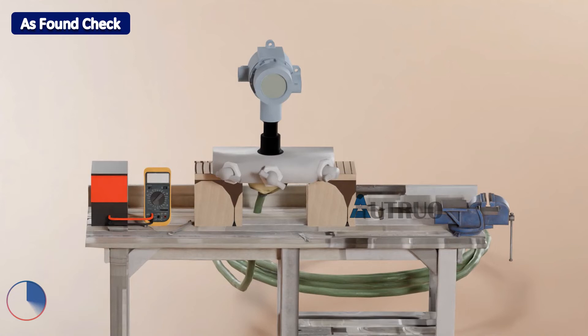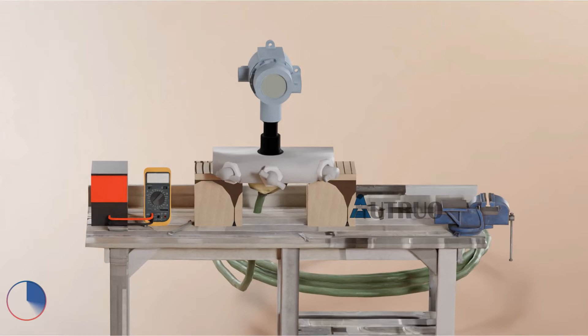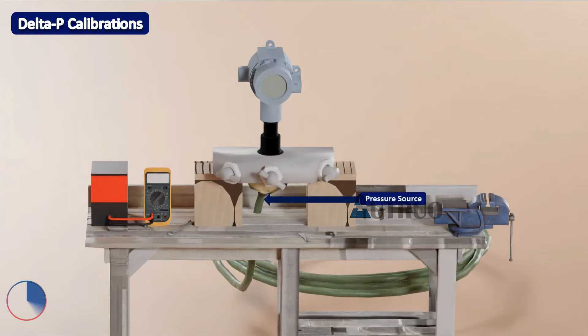We connect our pressure source once again. Again the pressure source must be accurate, because this will be the baseline of the transmitter behavior after it has been returned to the field. Again, we will also connect the digital multimeter in series with the transmitter. This is where the reading that is generated by the transmitter will be gotten. Now let's calibrate our transmitter.